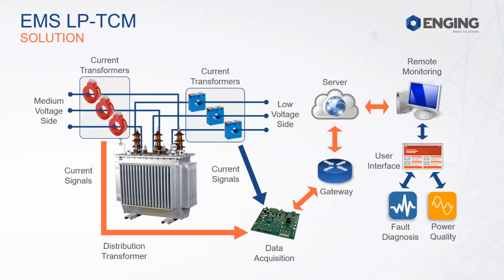This is the graphic. Basically, we are acquiring in the data acquisition platform the current signals of the transformer. We are sending them to a gateway. And from this gateway, we will send them to a server. One thing, the server can be either in Enging or can be in the client's server, as long as we have the space to run the algorithm. The idea, obviously, is to be able to pass the algorithm with a remote monitoring and then put it in a layout in a user-friendly interface, basically to reach a fault diagnosis and a power quality analysis.